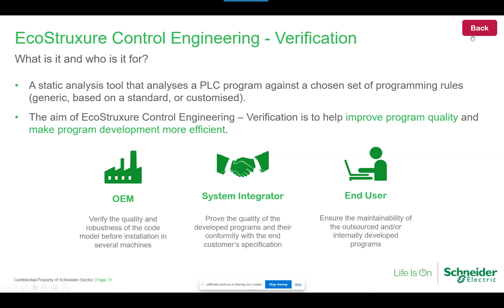So how does that happen? First, we look for dead code. We look for variable overlaps. We look for variables that are written before a read, which might cause a logic problem. We correct program execution order. We look at the naming convention that was created—does every variable follow it? That's done by the verification tool.